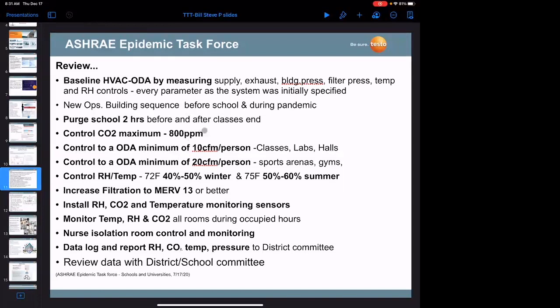This relates to how much fresh outdoor airflow you're bringing into schools. We want to increase outdoor airflow in the major congregating areas where there will be a lot of people in a confined space: classrooms, classroom laboratories, hallways, a minimum of 10 CFM per person. In larger venues on a campus, like sports gyms, sporting arenas, weight training rooms, cafeterias for lunch and morning break, any area with a large congregation of people, double that minimum outside airflow to 20 CFM per person.